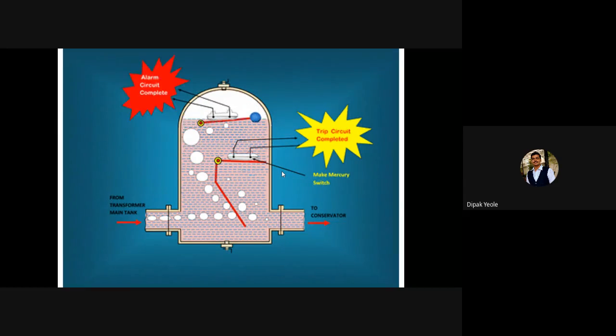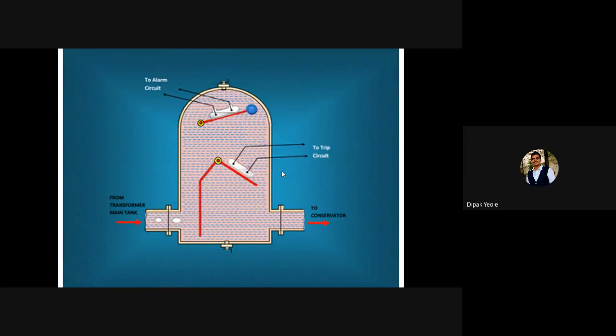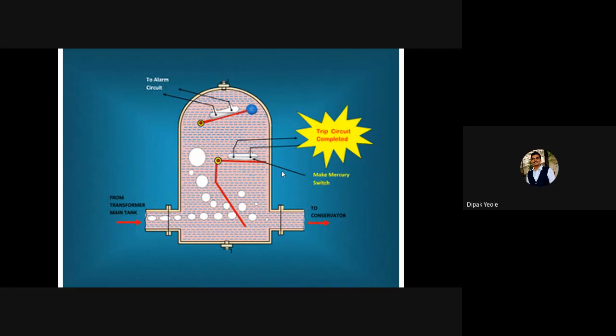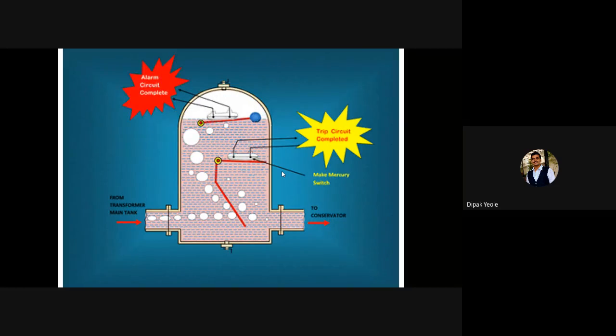But sometimes the Buchholz relay will not sense a small amount of gases. Only if the fault is of a major condition are the gases produced inside the Buchholz relay or transformer more significant.